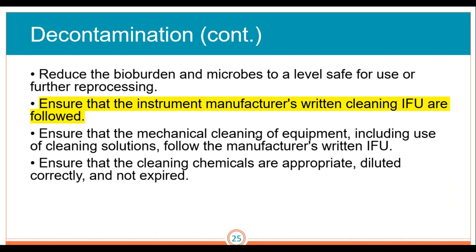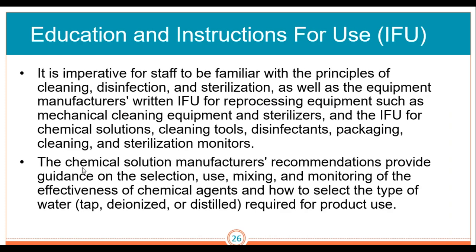Decontamination continued: we want to reduce bio-burden and microbes to a level safe for use or further reprocessing. Ensure that the instrument manufacturer's written cleaning instructions — the IFU — are followed, and that mechanical cleaning follows the manufacturer's IFUs. Ensure cleaning chemicals are appropriate, diluted correctly, and not expired. Many facilities use automatic diluters where the solution is pre-measured; most sterile processing departments should have that.